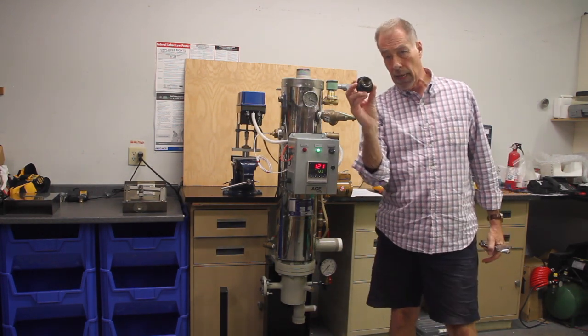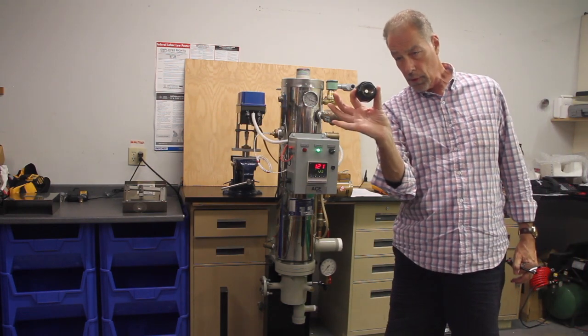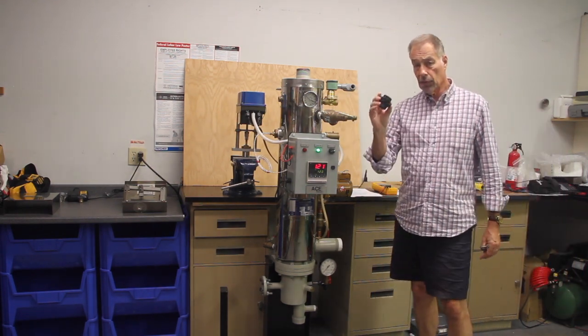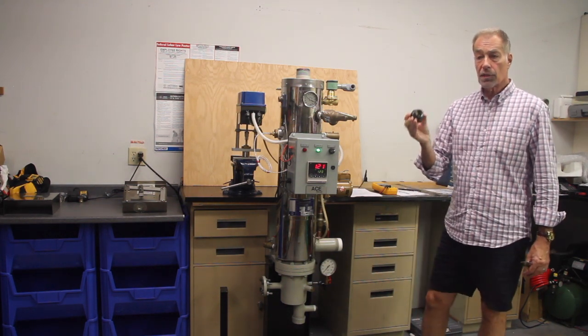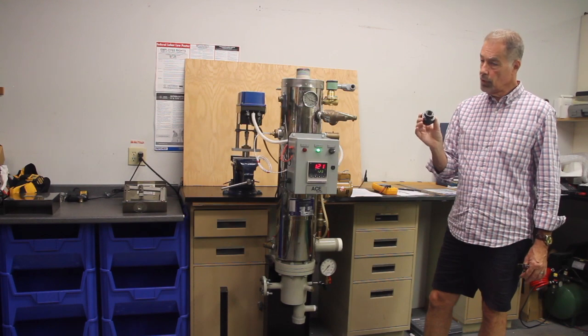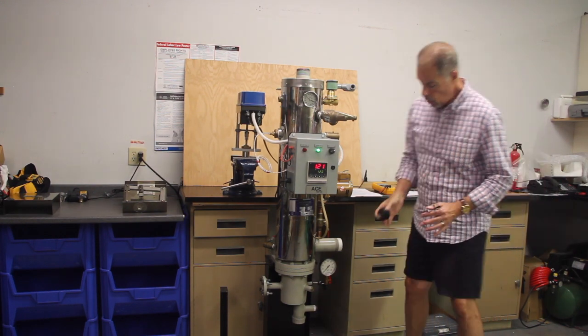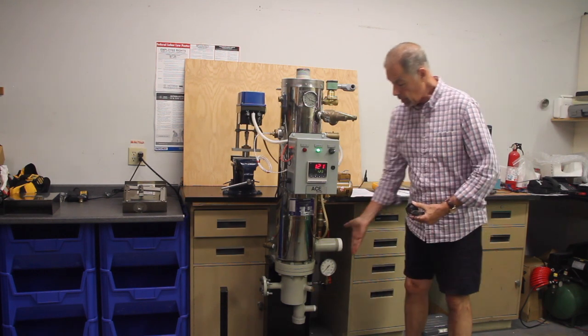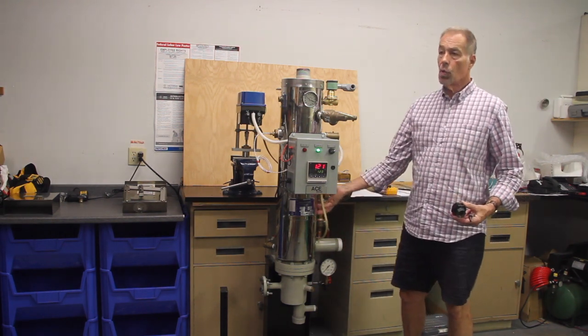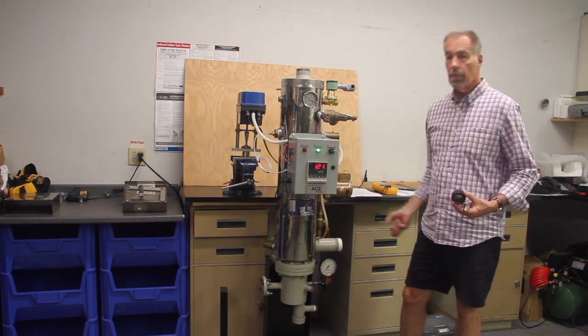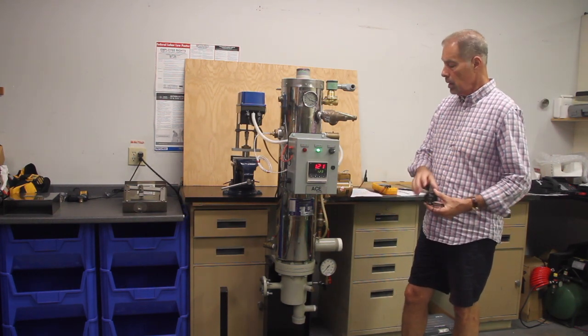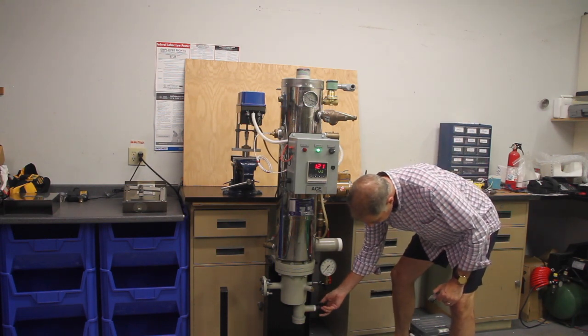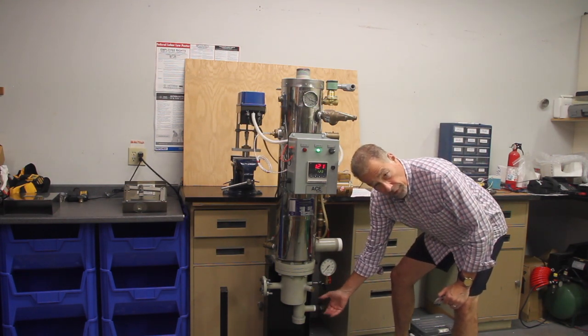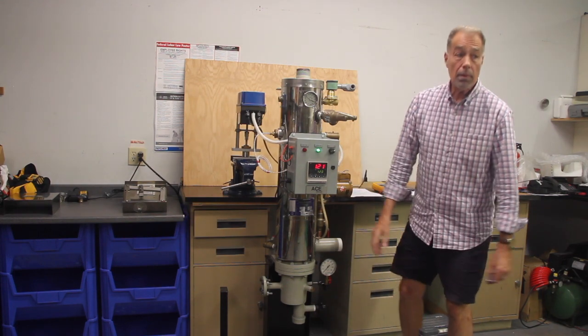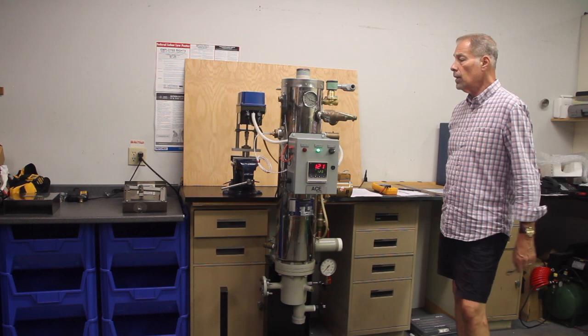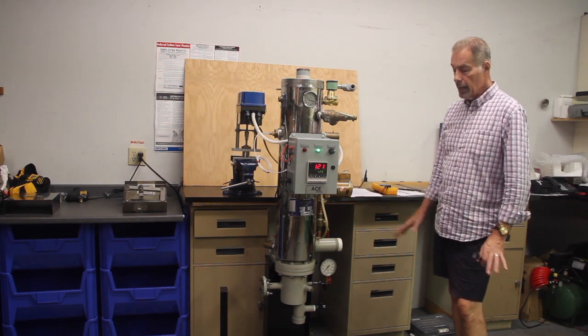with an orifice in that union. There's a brass orifice in this union, which is acting as what we call a simple steam trap. It's not a Venturi steam trap, don't confuse that. This is just a dam to hold the condensate from leaving the heater so the incoming cold water can take that 200 plus degree condensate and wring the BTUs out of it. Take all the heat out, and it just makes for a much more efficient device, and it saves your condensate receivers from flashing steam, pitting the impeller, cavitating the impeller. It's a great device. It's a great design, and there are no moving parts.